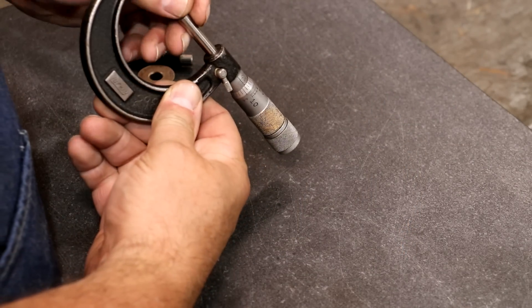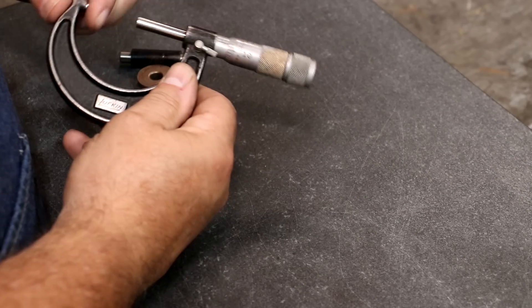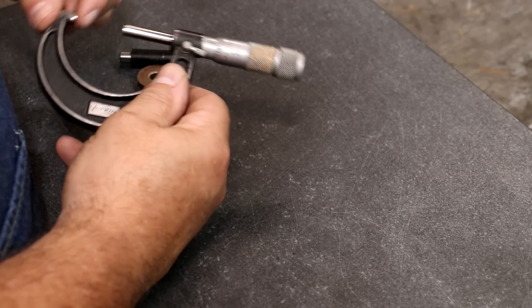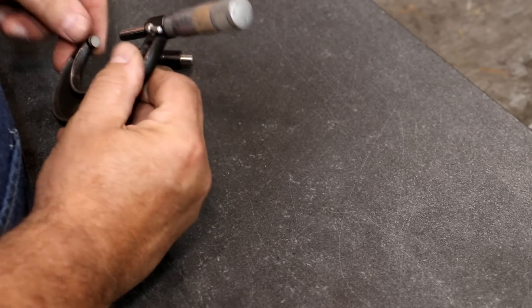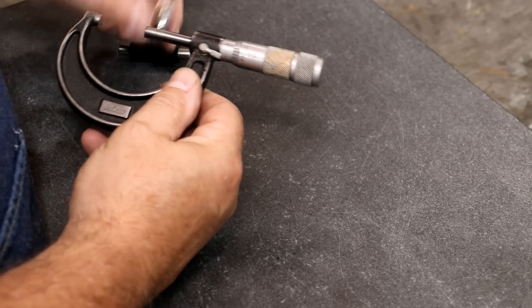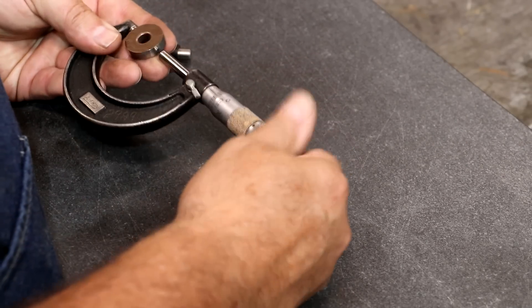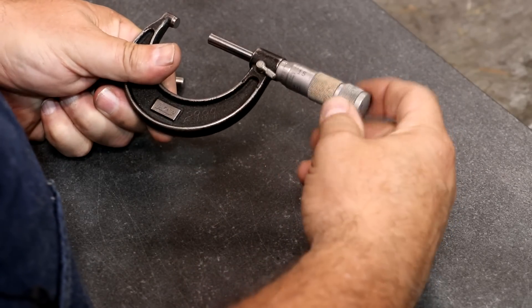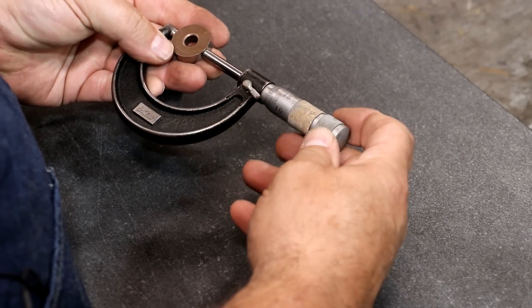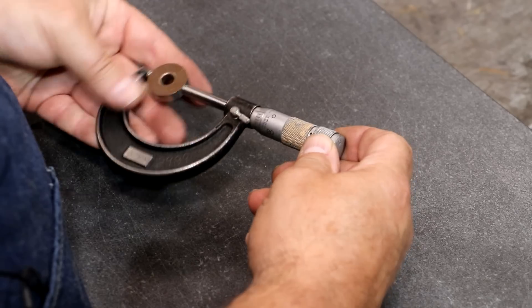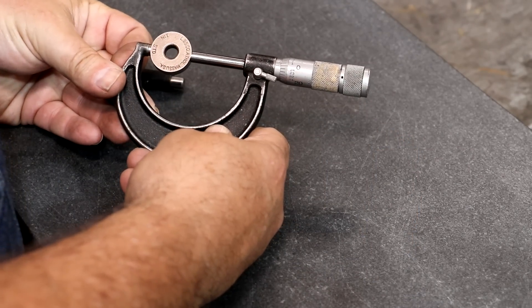So next I've got a one to two inch micrometer. Again, first thing I always do, even when I'm using these is I just check the anvils and make sure they're clean. And on a larger one, I can get my finger in there and I'll just usually just wipe them. But again, we're going to use the bottom end of this one. Remember, the bottom end of this one is one inch, so one to two inch micrometer. So let's run it down here. We use our one inch standard and it's reading right on zero.